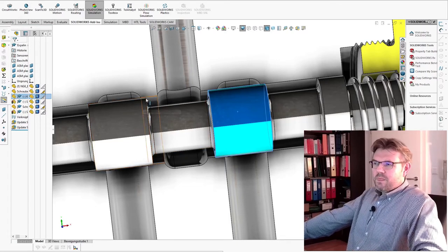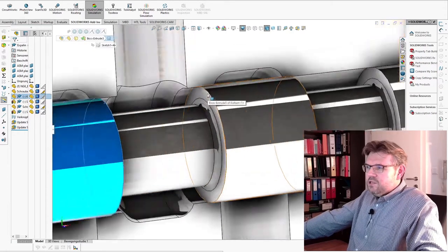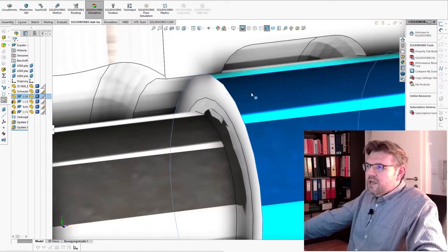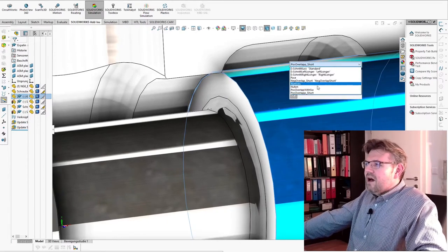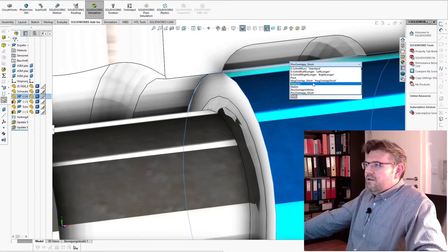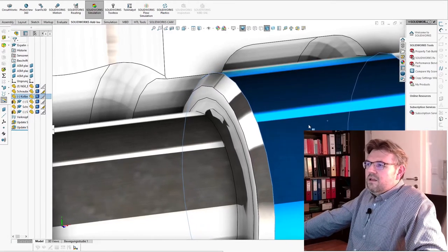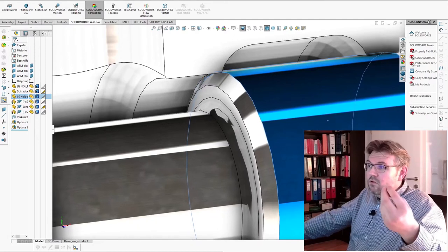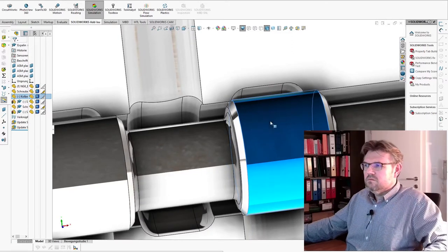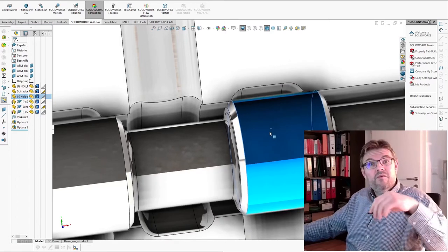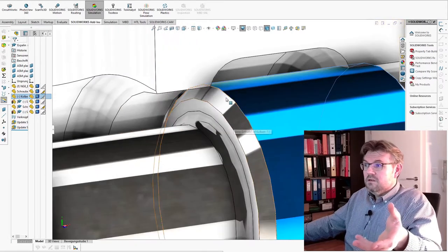Whenever these edges here, these are called contour edges, whenever these edges of the pistons are entering the chamber, something is changing, they're opening a gap. There are also pistons out there which have different endings, like this. Then you see that the behavior of opening the gap looks different. Here the edge is broken, simply. So the flow characteristic will be different. This is just done by changing the edges of the piston inside.